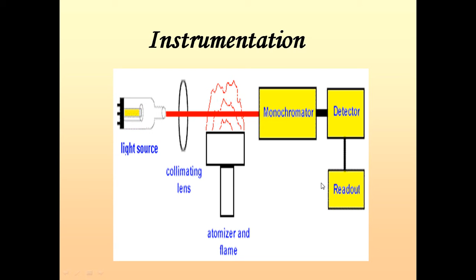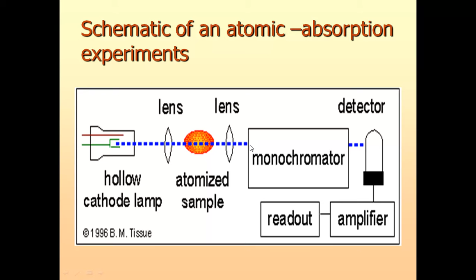This is the basic scheme of atomic absorption with a hollow cathode lamp. The sample gets atomized, and ultimately this beam is passed to the monochromator, then detected, amplified, and basically we get the readout. This is the original picture of the atomic absorption spectroscopy instrument. This is the light source which contains the cathode lamp, and this is the sample where the metal is present in the ground state.